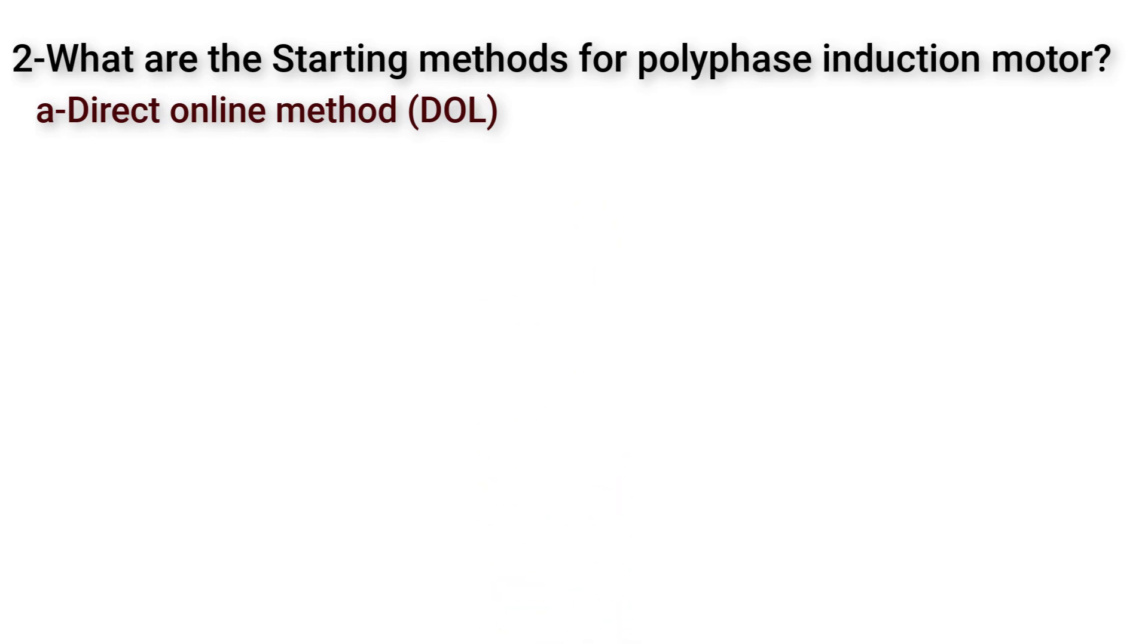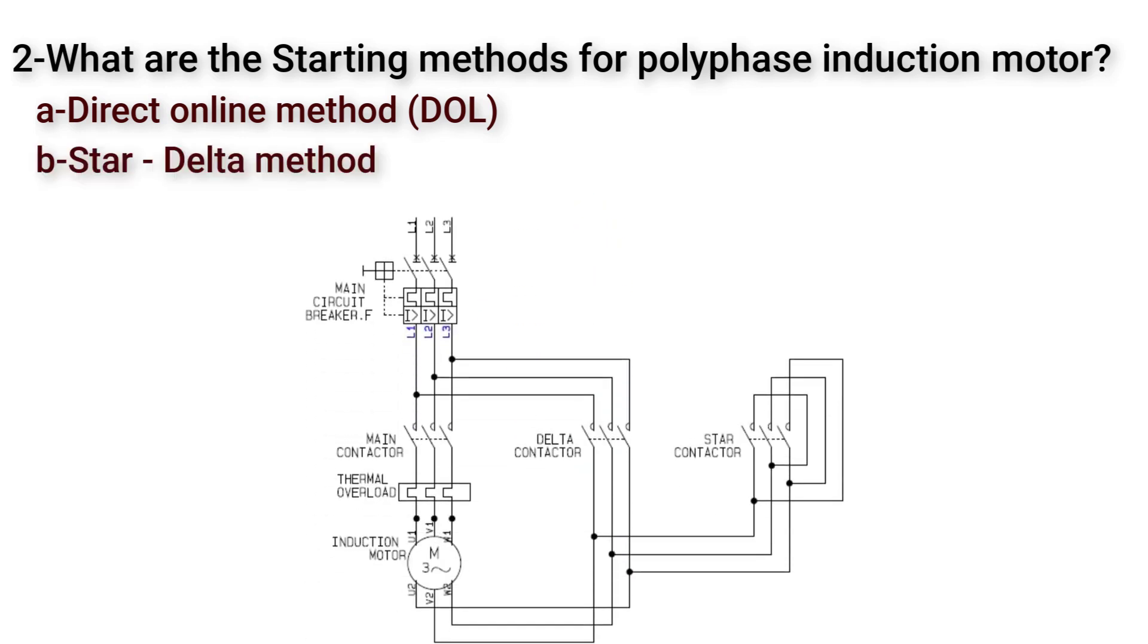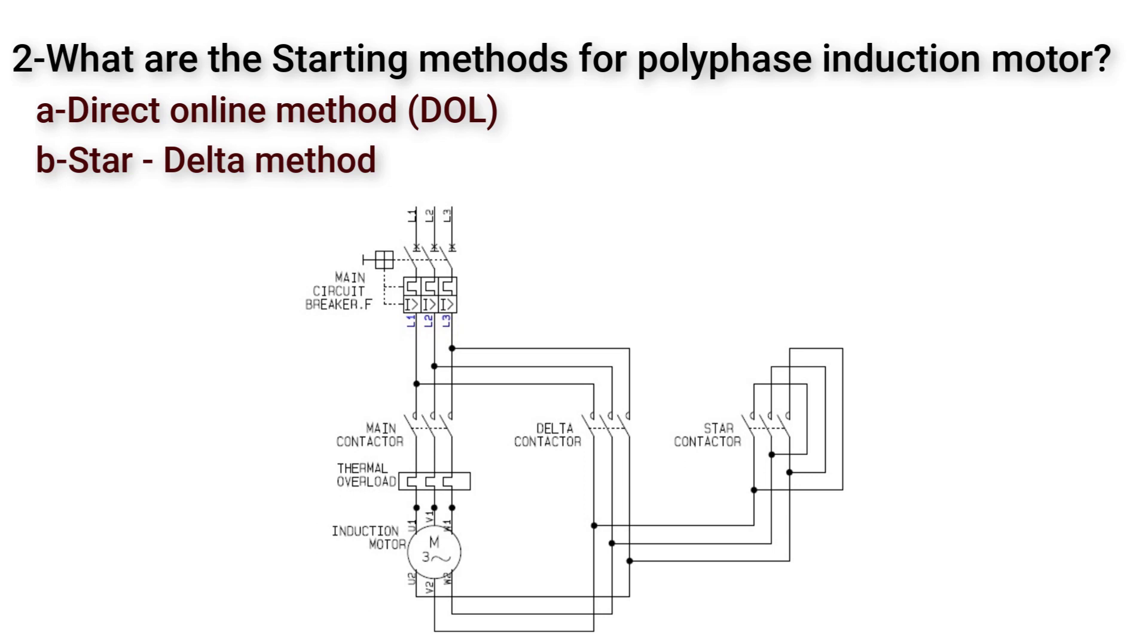Second method is star-delta method. Here we use contactors to start the motor in star connection which will reduce the inrush current. After starting, the contactors automatically change the connection of motor to delta connection. Note that this method is used for motors designed to operate in delta connected winding.